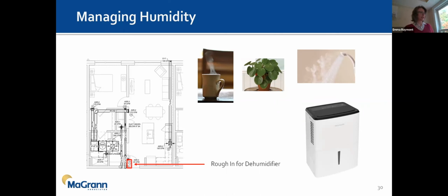Last item here, just to touch on that humidity piece. So, you know, Minotair apparently is working well for that. And I'm really glad to hear that. I'm looking forward to being able to try one of those somewhere. Our solution with this constant run ERV that does some low level dehumidification is, I think, going to be very effective in the building that we designed that for.